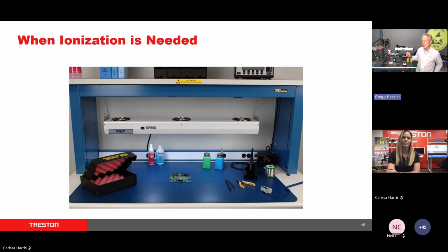But also, this is one thing that a lot of people don't think about. It's not just about neutralizing the charge, it's about keeping that charge from being as great as it could be. So something that might be 5,000 volts like this paddle maybe only charges up to a couple of hundred volts until it's completely neutralized. That's right.